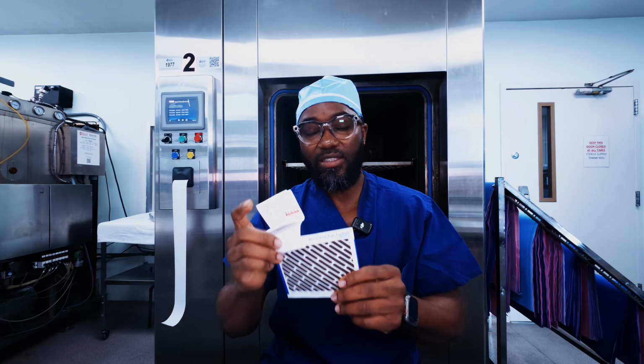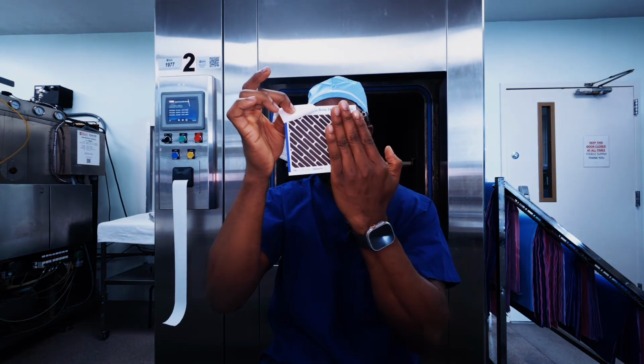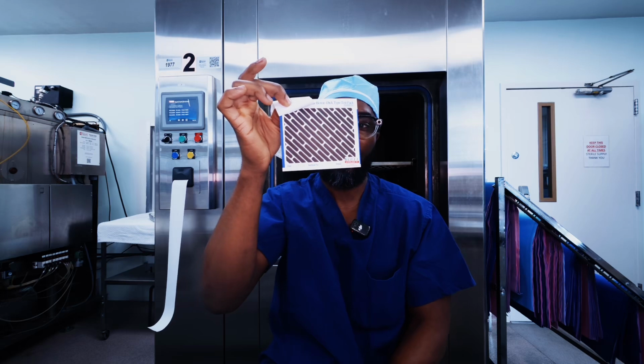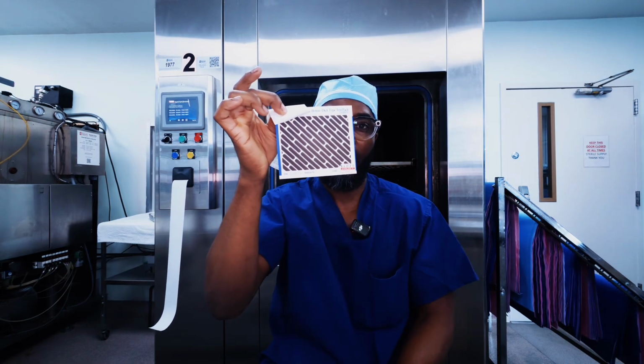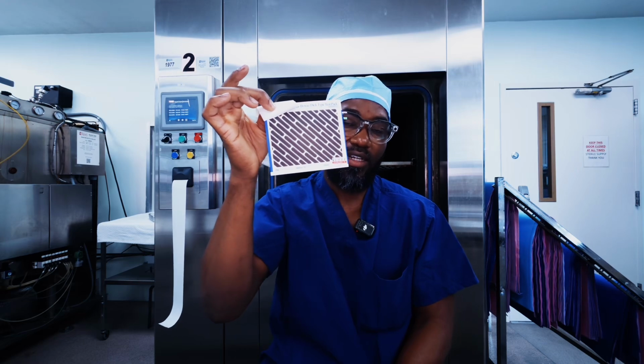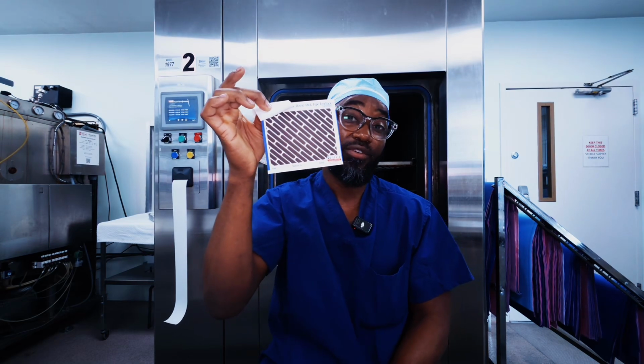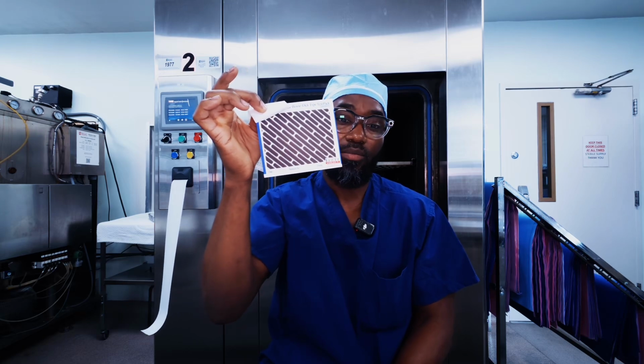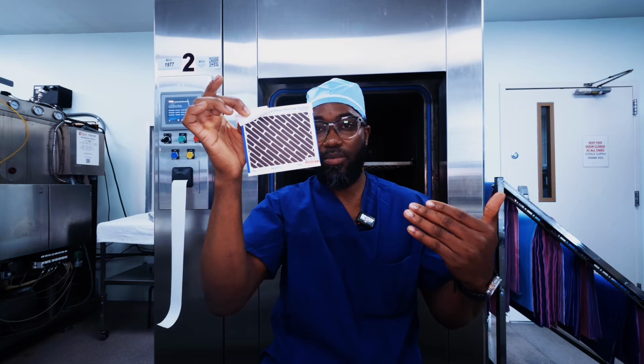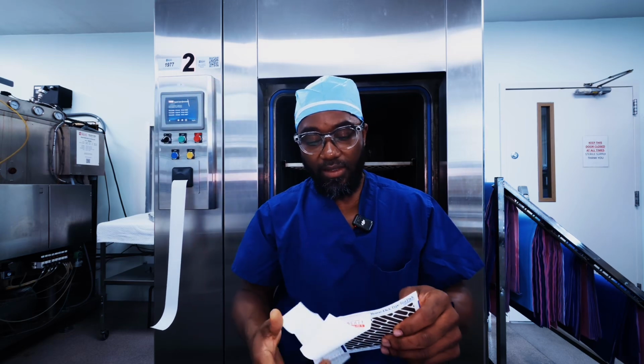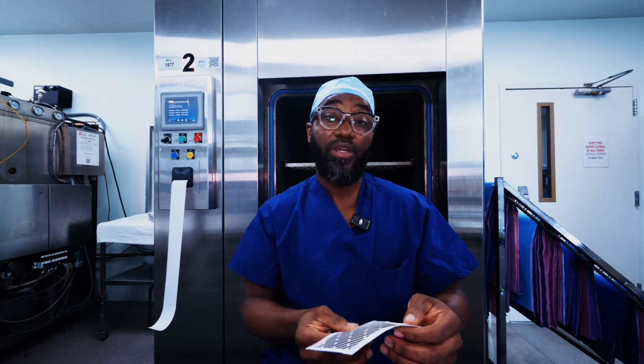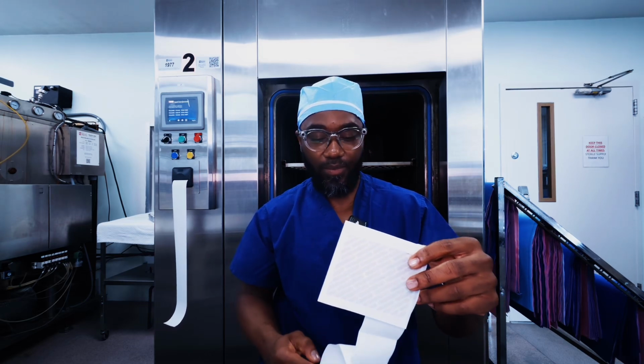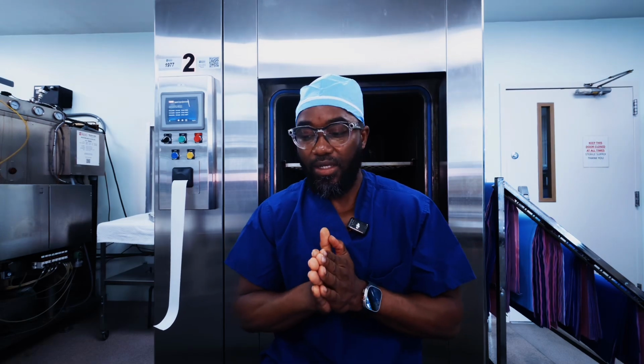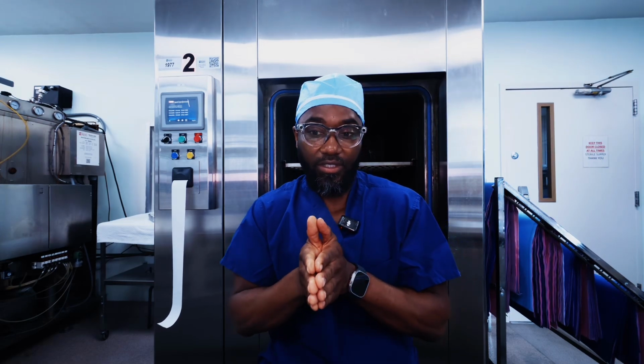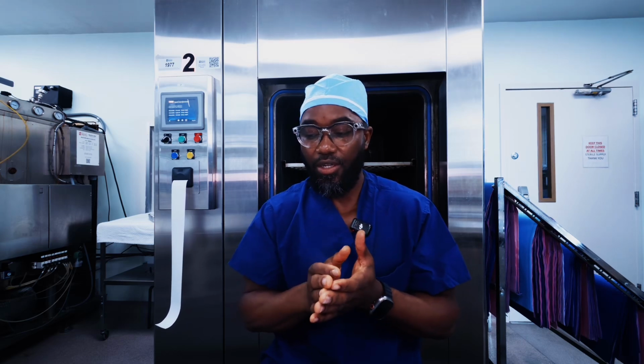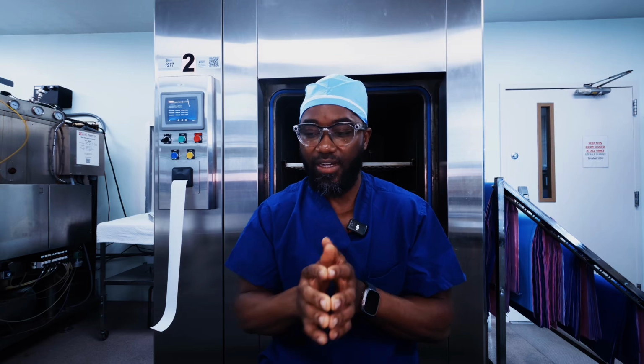When you run your Bowie-Dick test, your results should look like this, an even black coating across this result page. If there is a circle in here that's gray, it means that the autoclave is not taking out air properly, and it should be referred to your supervisor or the maintenance group to make sure that this sterilizer is properly getting air out. The second test is done along with your first load of the day. It is recommended that whenever you run your first load of the day that includes medical instrumentation, you run it with a process challenge device.